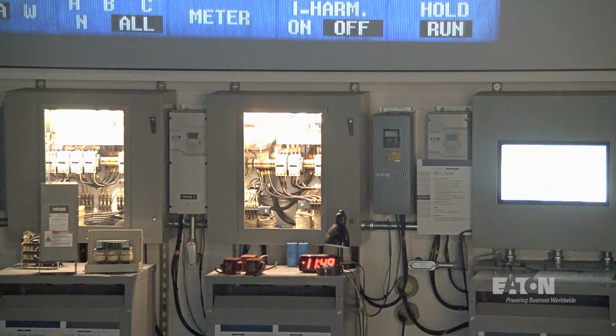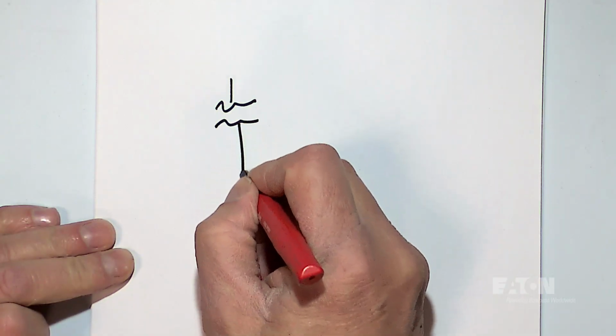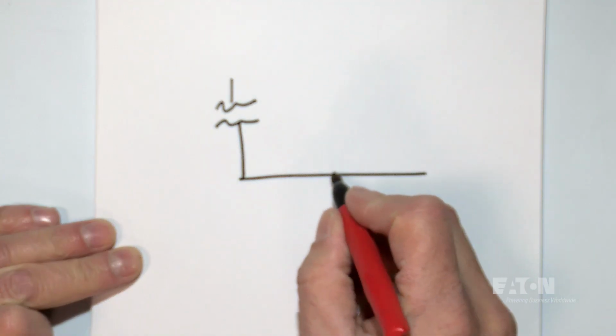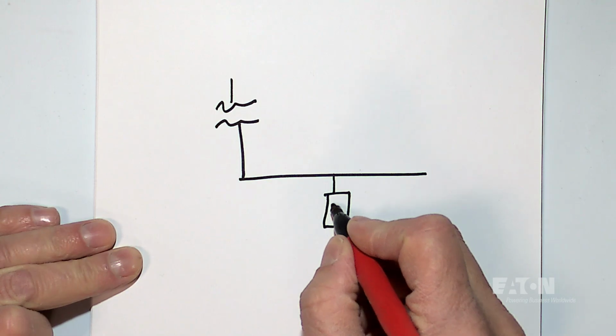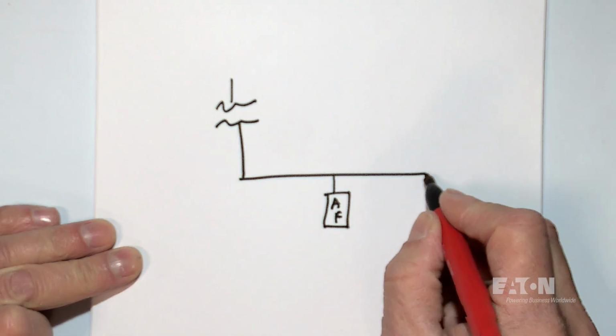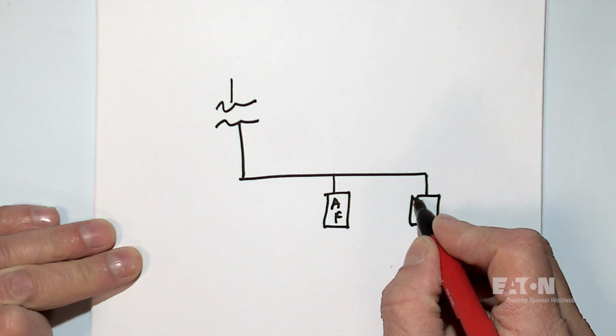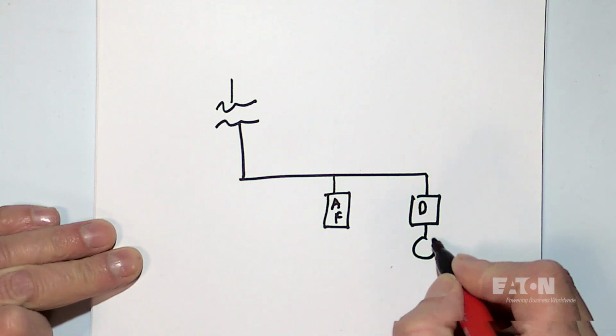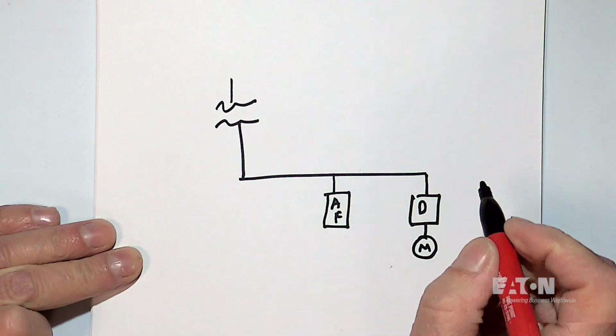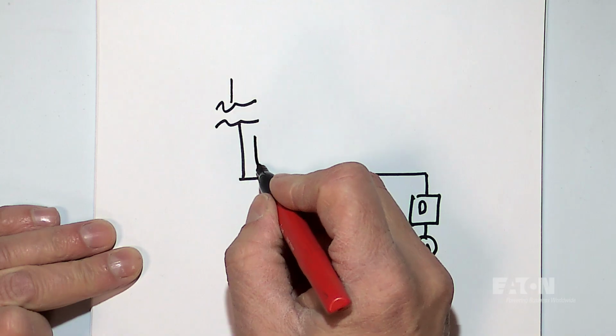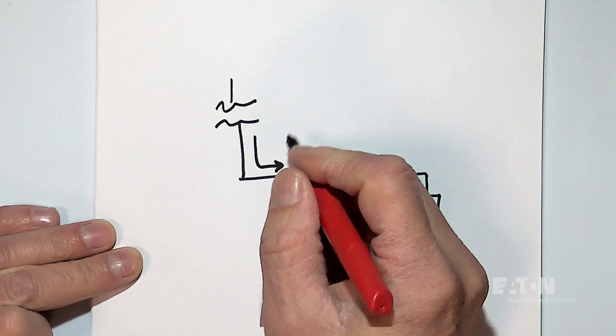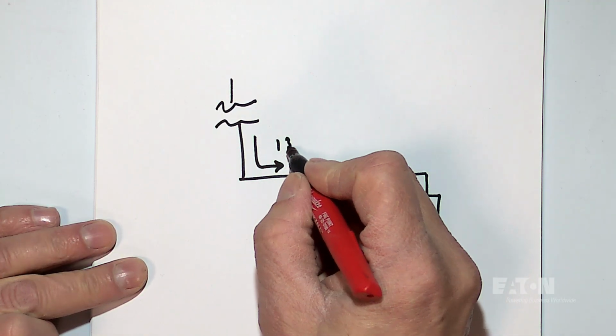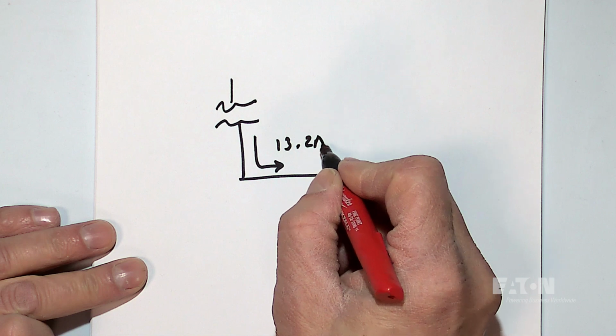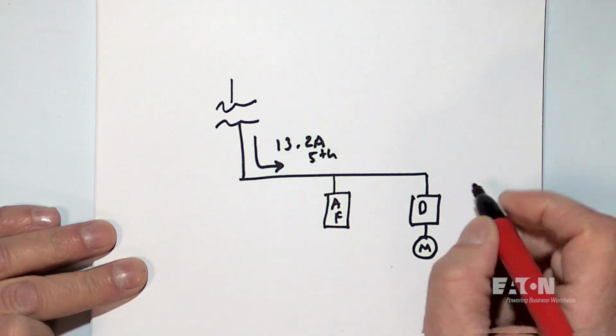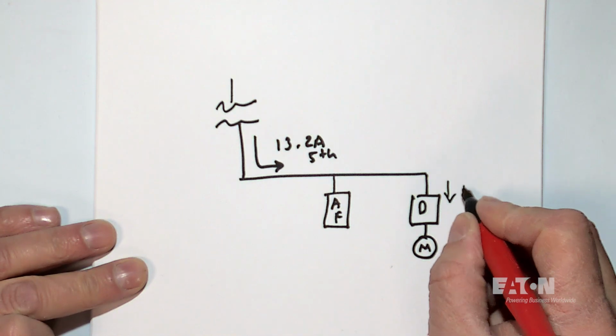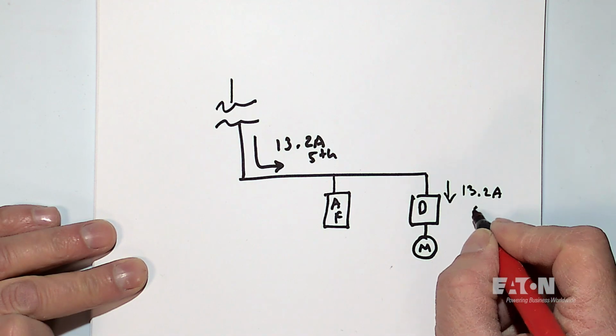So again, what we had was we have our source transformer. We have a busway here where we have an active filter here, and then we have our drive, our VFD here, feeding our motor. Now, the first time we had a certain amount of harmonic current coming this way, a fifth harmonic, and it was on the order of 13.2 amps of fifth harmonic current. And then if we measured over here, we had roughly the same, 13.2 amps of fifth harmonic current.